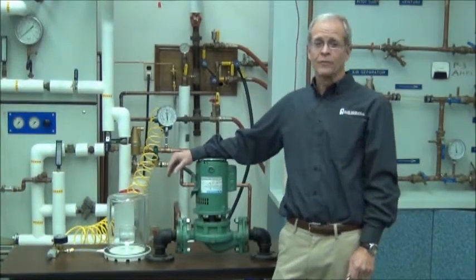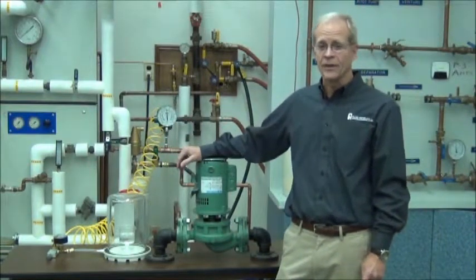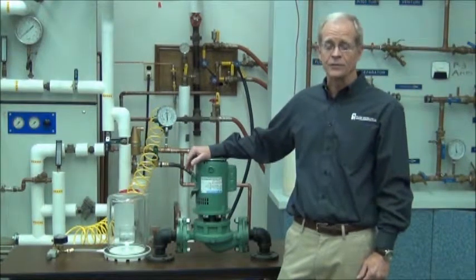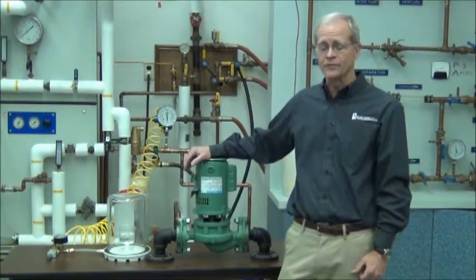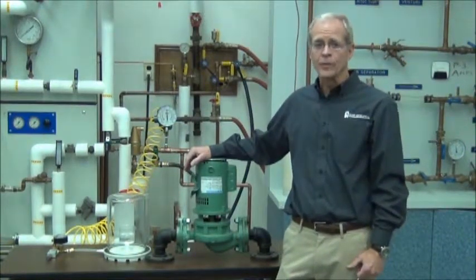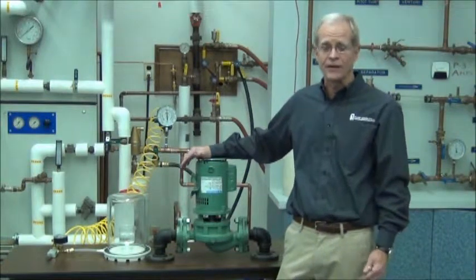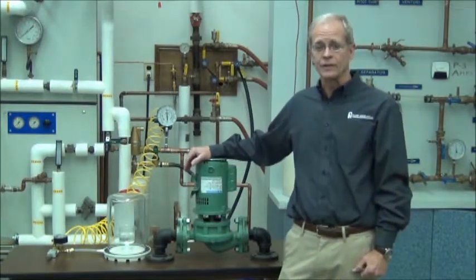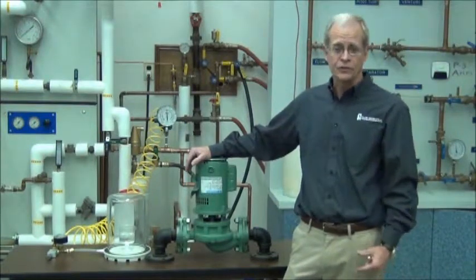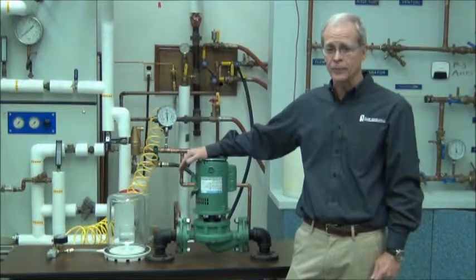In our experiment, we showed that according to Henry's Law, dissolved gases will come out of solution. And according to Boyle's Law, the volume of those gases will increase, resulting in some larger bubbles. The application for that in our industry is when we're pumping water from a cooling tower that has a lot of dissolved gases. The gas would be air in that case. And as the water enters the suction side of the pump, we have a pressure reduction, which results in some of the same things we showed in our experiment.